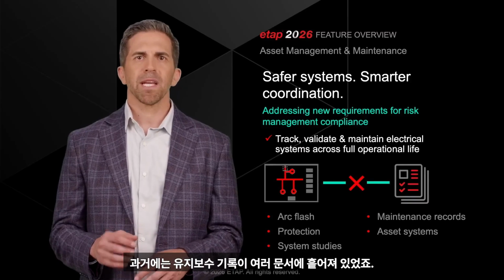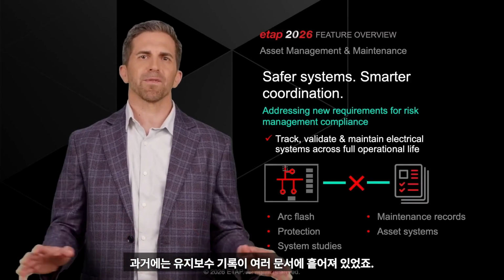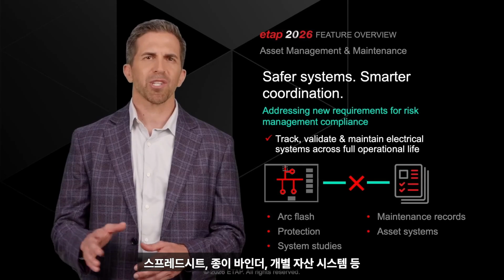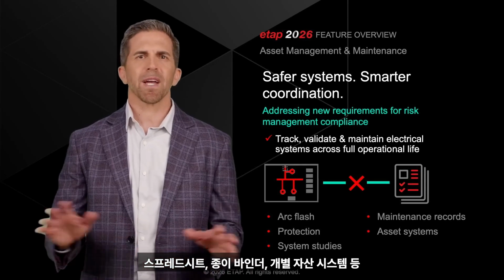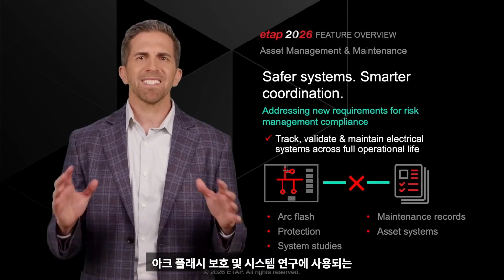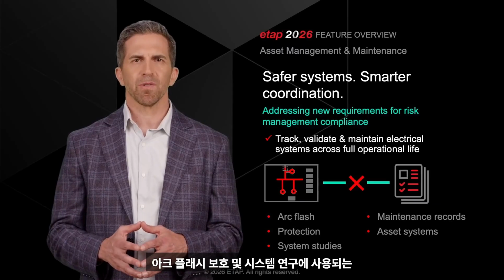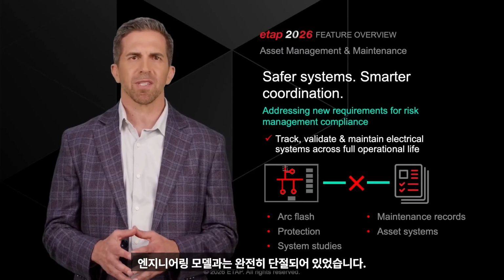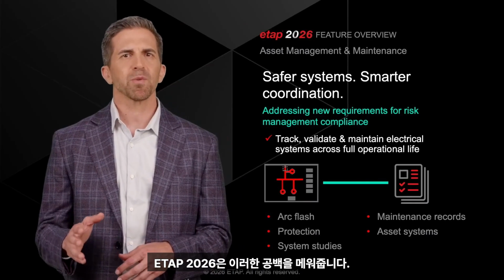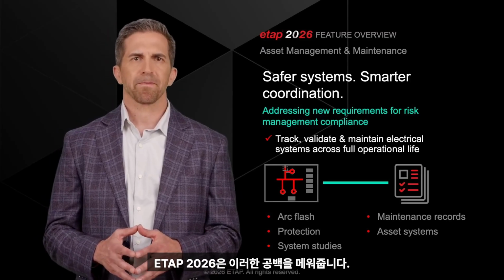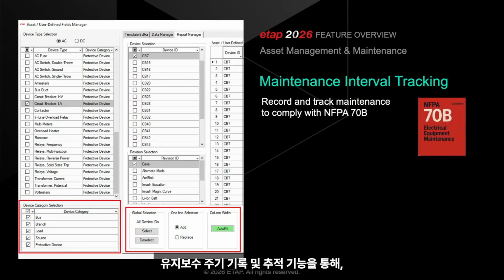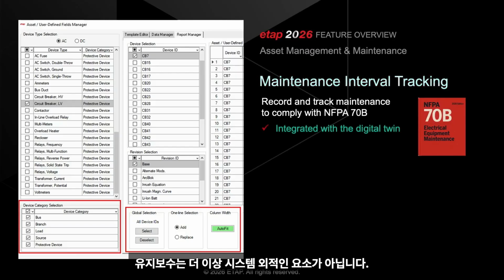In the past, maintenance records were scattered across many different documents: spreadsheets, paper binders, separate asset systems, completely disconnected from the engineering model used for arc flash protection and system studies. ETAP 2026 closes the gap. With record and track maintenance intervals, maintenance is no longer external to the system. It becomes a part of the digital twin.